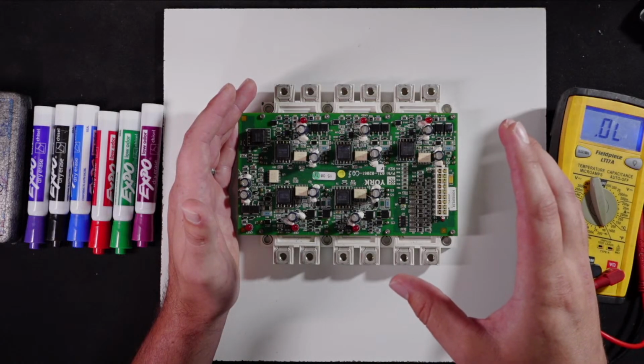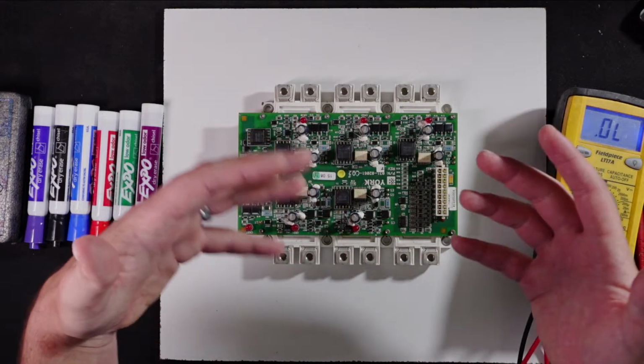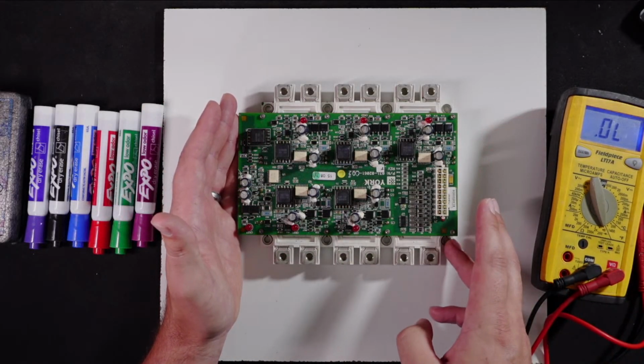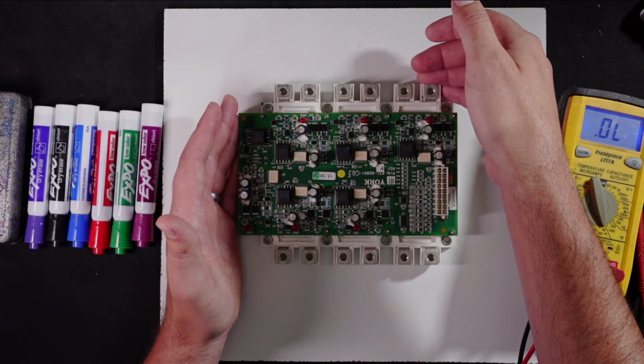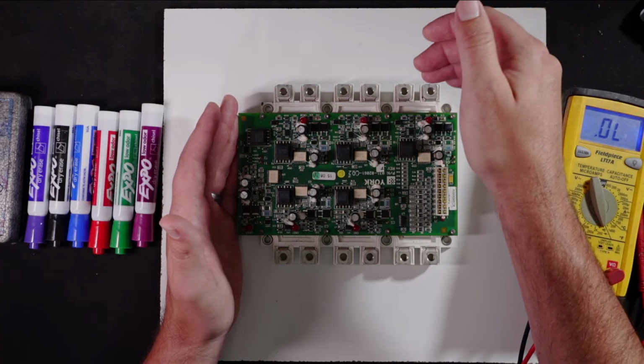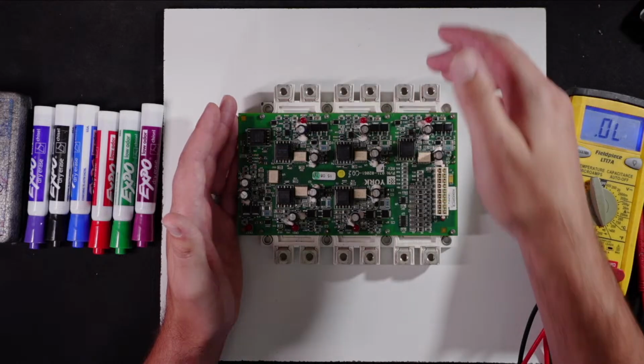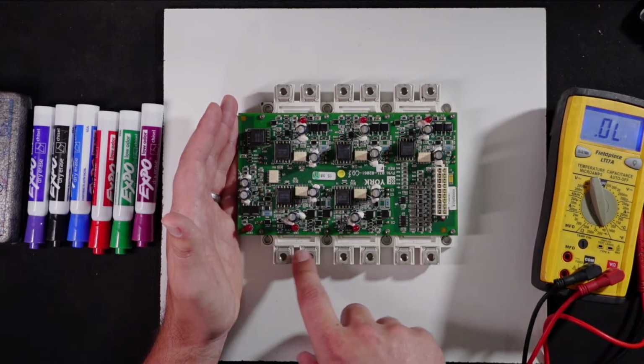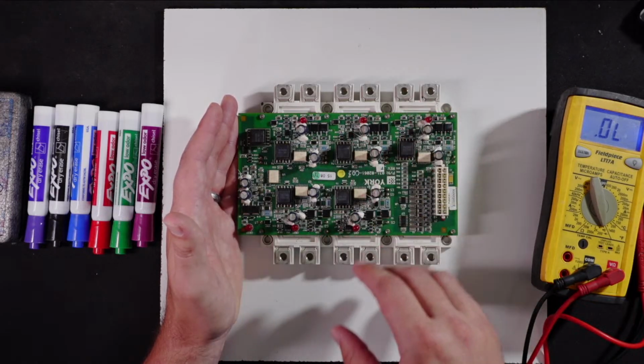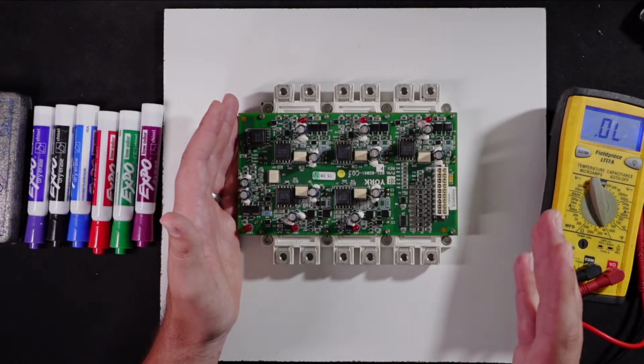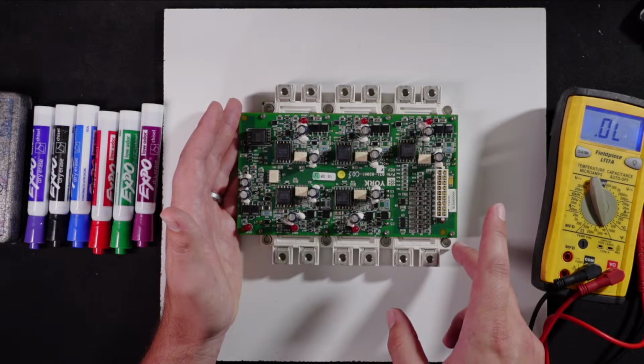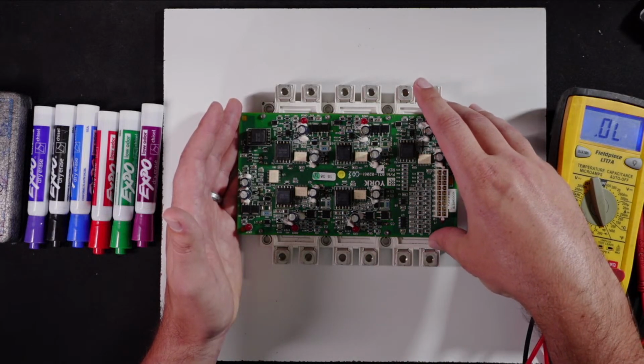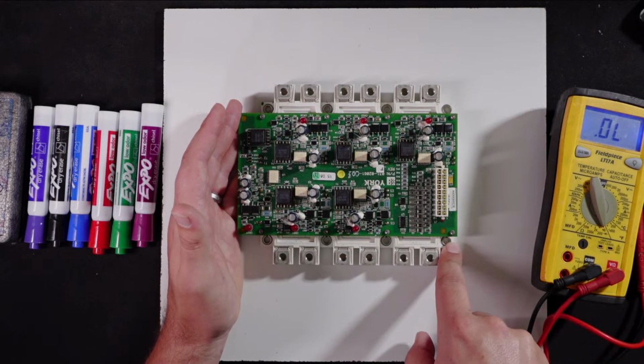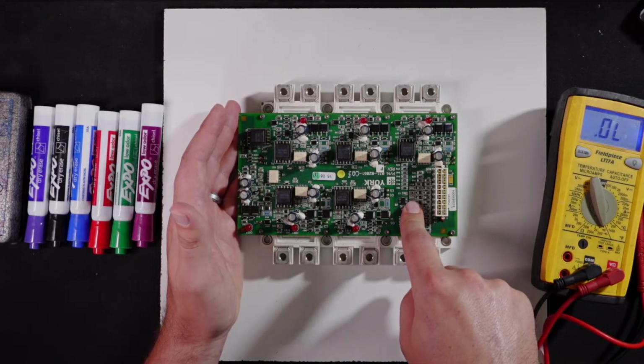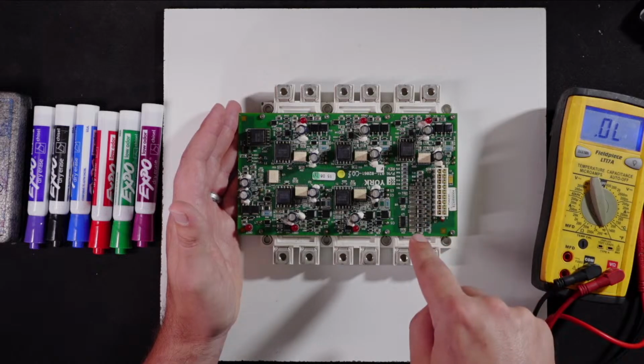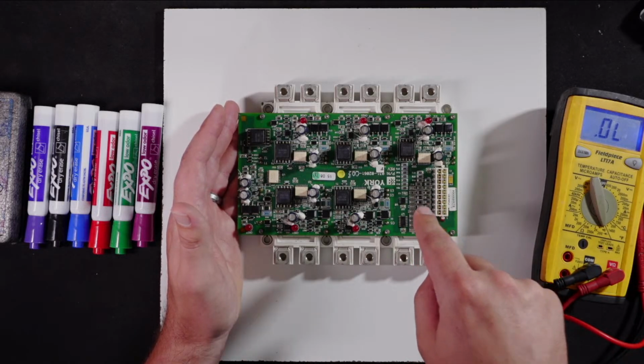Yeah, I'm thinking through all the different ways that these can fail. So heat, or you can have a DC bus voltage that is just wrong coming in. You could have too high of a DC bus, too low of a DC bus. Those will typically trigger alarms. You could have a motor failure or a short to ground, something like that, that could potentially cause an issue here. But the most common I see comes back to either a cooling issue or the silicon just breaking down with time, which, even if the temperatures were maintained perfectly, is just going to happen. That is a failure point of these. This silicon will break down, will begin to have issues, and eventually just fail.